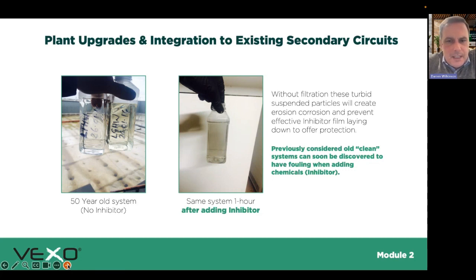You have to be pragmatic about how you approach the secondary side. If you've got an old system, we typically promote a passive, non-flush cleanse, using filtration with non-flush additives if you can. Sometimes old systems just get an inhibitor. It's not ideal, but we don't want a sprinkler-system effect on that secondary side.